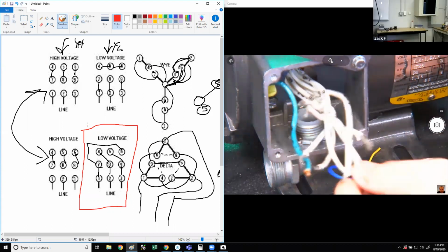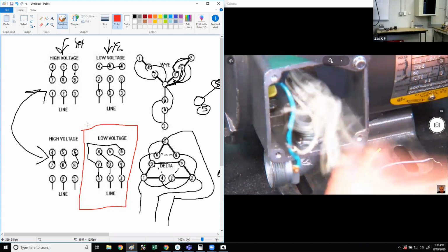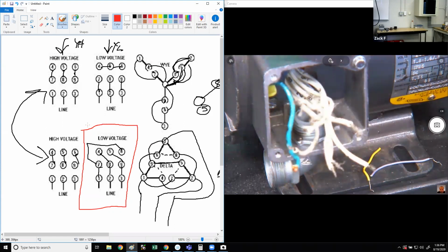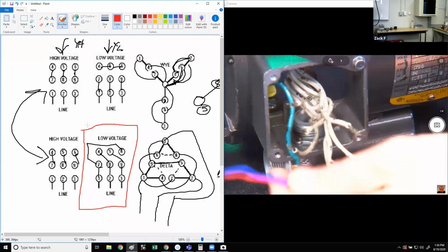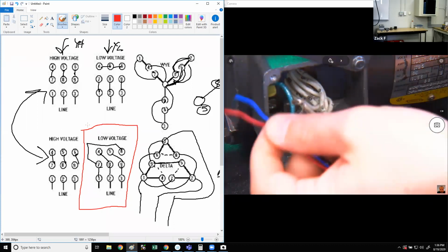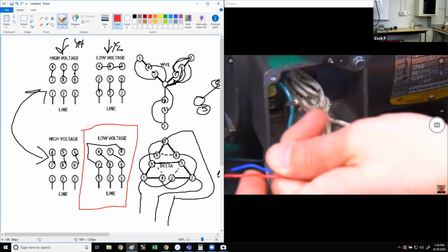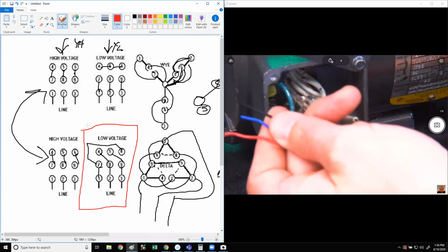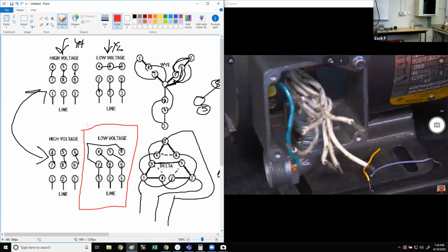All right, so my 3 wires coming in from the motor starter, I'm going to use black, red, blue. So if I have 3-phase low voltage, you would guess that these are the colors being used. 3-phase high voltage, if it was 480, should I have black, red, and blue coming into this thing? What colors should I have? Brown, orange, yellow. Perfect, very good.